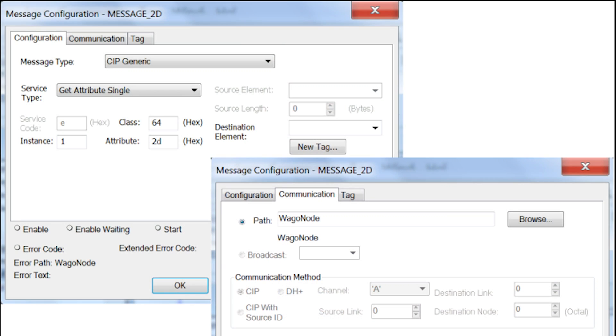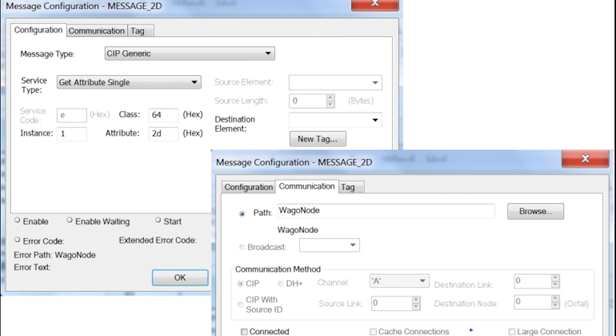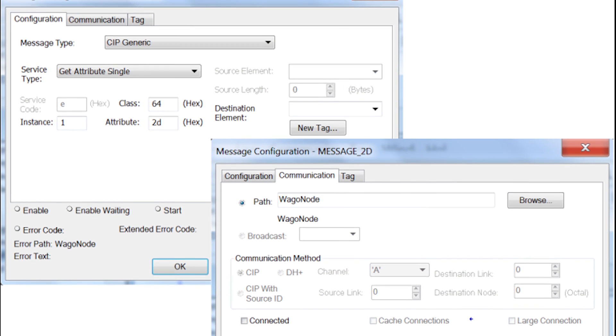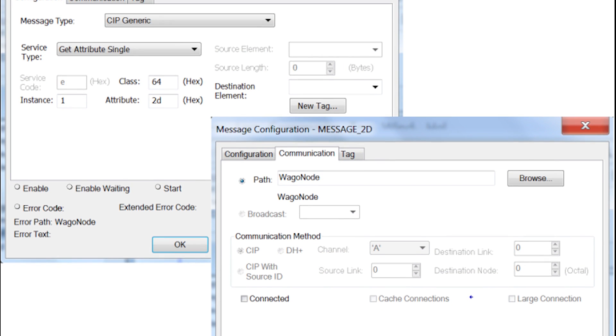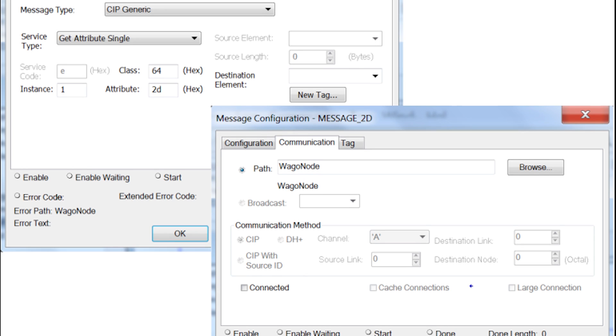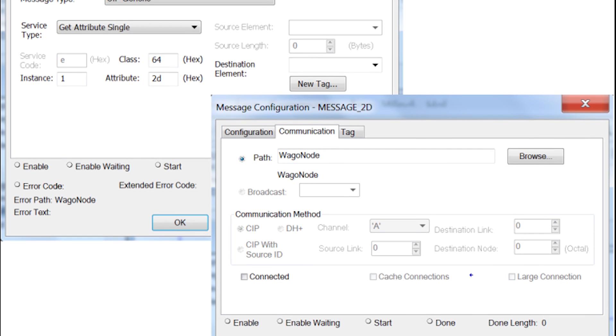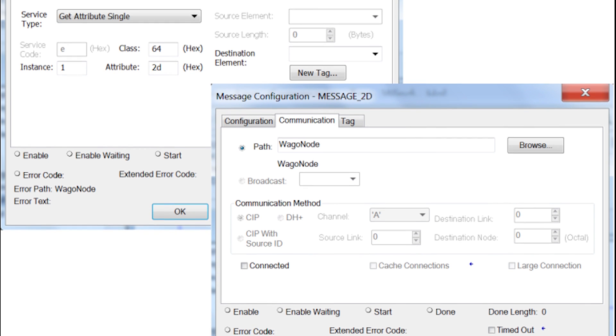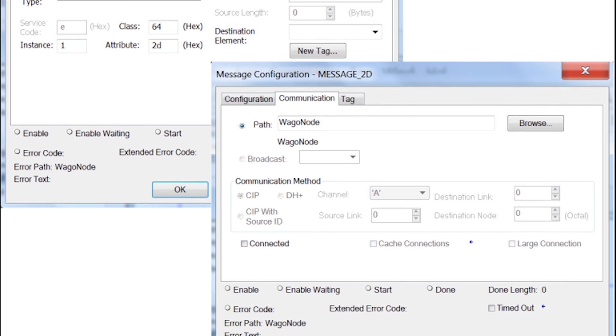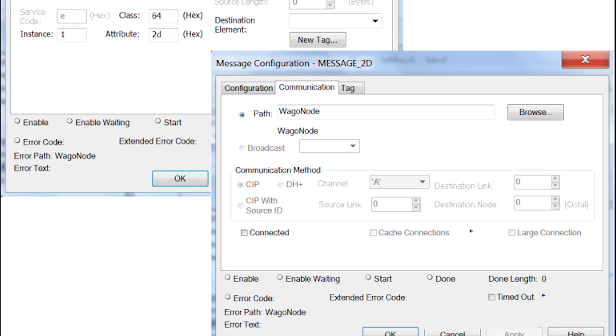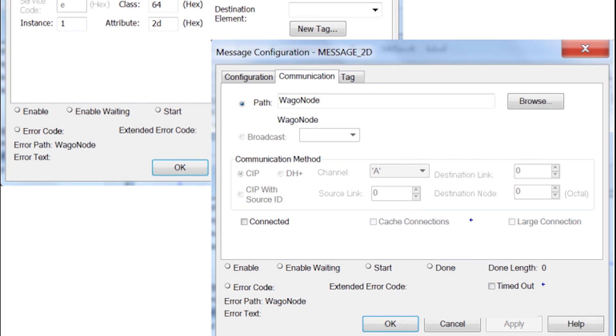Here's a brief explanation of how this can be accomplished. Wago's Ethernet IP bus couplers and controllers provide a coupler configuration class that contains important process parameters, such as coupler status, the IO-LED error code, and more.